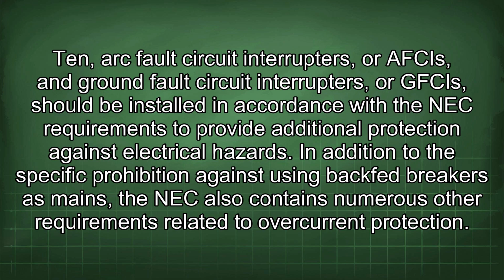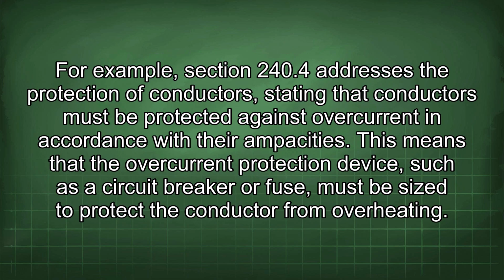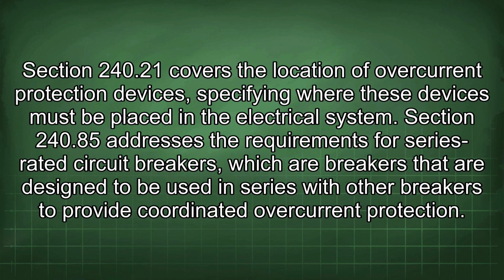In addition to the specific prohibition against using backfed breakers as mains, the NEC also contains numerous other requirements related to overcurrent protection. For example, Section 240.4 addresses the protection of conductors, stating that conductors must be protected against overcurrent in accordance with their ampacities. This means that the overcurrent protection device, such as the circuit breaker or fuse, must be sized to protect the conductor from overheating. Section 240.21 covers the location of overcurrent protection devices, specifying where these devices must be placed in the electrical system.